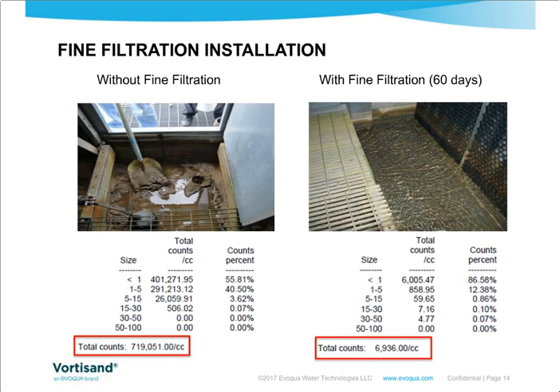Now, if we go a step further and understand not just the visual and not just from a TSS perspective, but from a particle size perspective, and we look at the tables below here, you actually can see how that particle size compares. On the left here, the water that was not filtered with fine filtration, over 90% of the particles are below 5 microns in size. And if you look at the total count, total particles in that water, you're looking at almost 720,000 particles per cubic centimeter. Once fine filtration was installed, after 60 days of operation, that total count dropped from 720,000 all the way down to almost 7,000 counts per cubic centimeter, a drastic improvement by removing those small 5 micron and less particles. Very important to understand the data to understand your water quality.